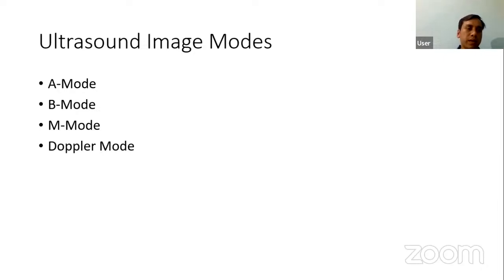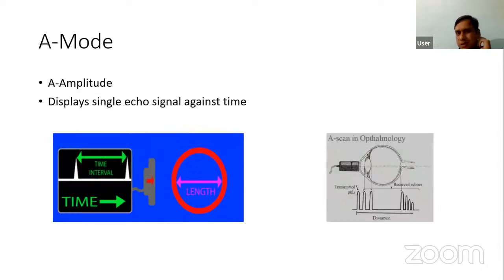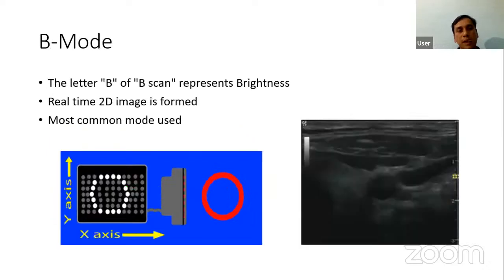A mode, B mode, M mode, and Doppler mode are the 4 common modes which are used. A stands for amplitude. It is the simplest mode, though we do not use it, but ophthalmologists use it very commonly to measure the length of the eyeball. What it does is display only a single echo signal against time. So we don't commonly use this mode, only the ophthalmologist uses it just to measure the length of the eyeball.